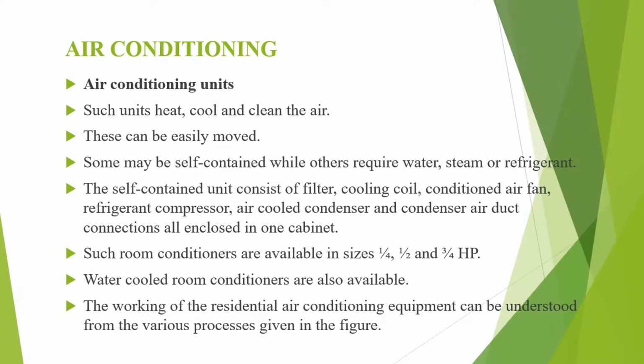Air conditioning units. These units heat, cool and clean the air. They can be easily moved. Some might be self-contained while others require water, steam or refrigerant and other equipment. The self-contained unit consists of filter, cooling coil, conditioned air fan, refrigerant compressor, air-cooled condenser and condenser air duct connections, all enclosed in a single cabinet.